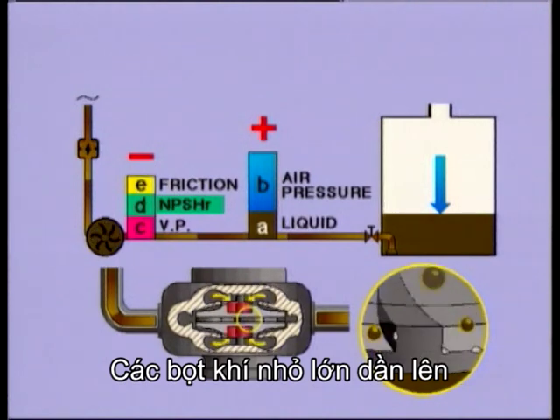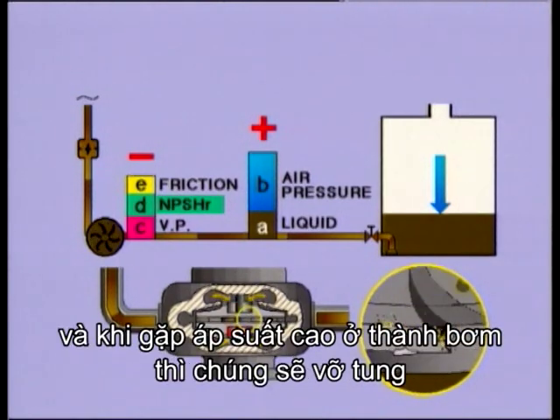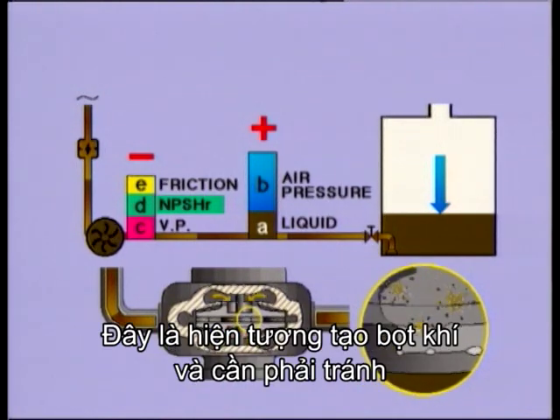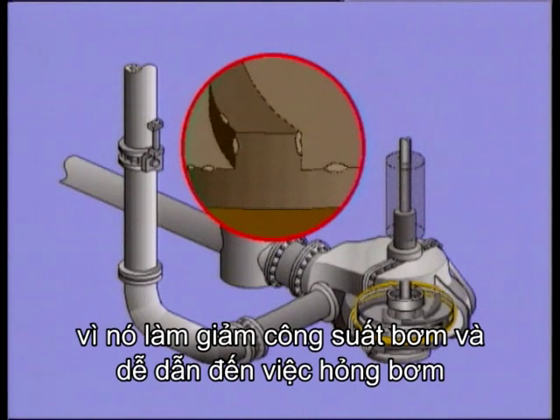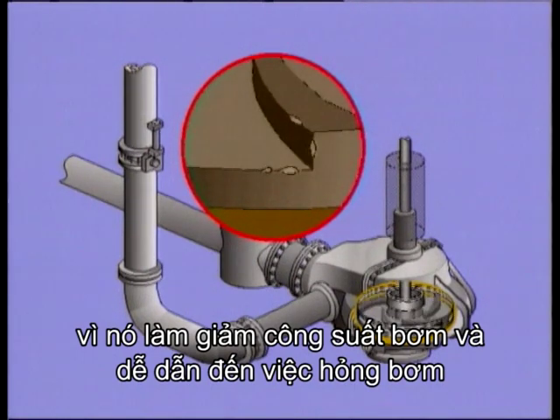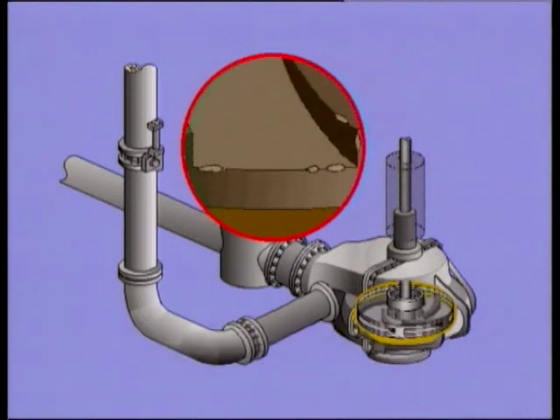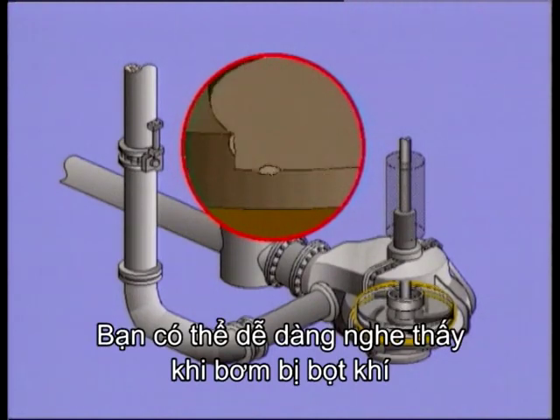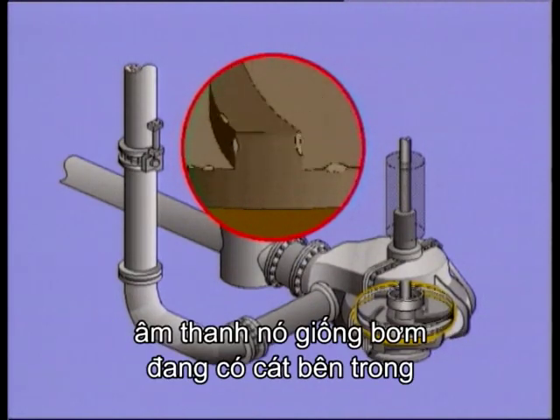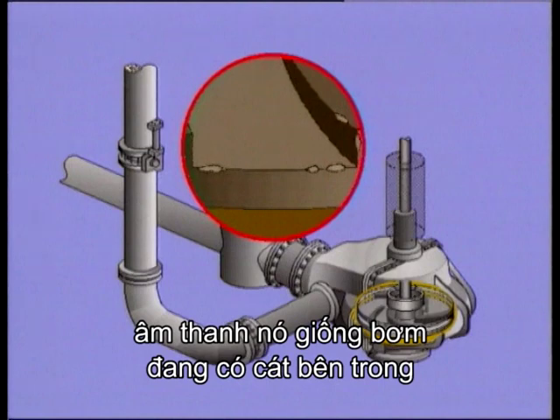Small bubbles grow, and when they meet the higher pressure in the periphery of the pump, they collapse. This is cavitation and must be avoided, as the capacity of the pump will be reduced and it can easily be permanently damaged. You can easily hear when a pump cavitates. It sounds like you're pumping gravel.